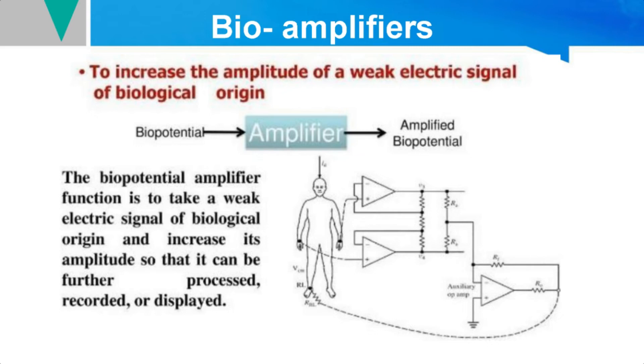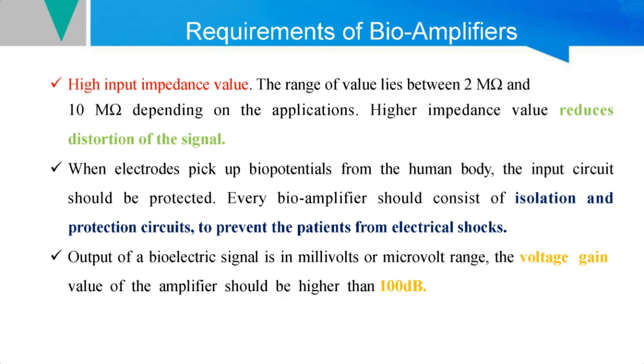There are certain requirements for designing bioamplifiers. The first basic requirement is that it should have a very high input impedance. A high input impedance reduces distortion of the signals. Whenever biological signals are picked up from the patient's body, there may be distortions or noise added due to the environment. If the system maintains a high input impedance between 2 megaohms and 10 megaohms, it can avoid noise and distortion in the signal.